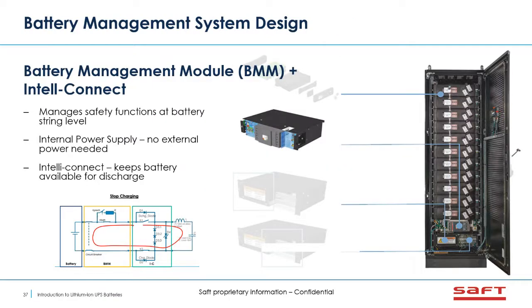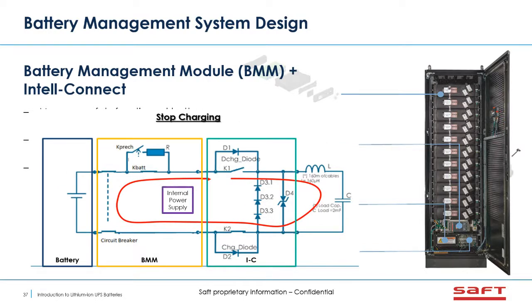A little bit about our BMS: this is where all the safety functions are built in. The key thing we designed into our system is that it has an internal power supply, so we don't require any external power supply going to our cabinet. The other thing unique to our product is IntelliConnect, which keeps the battery available for discharge. If I blow up the schematic here, the dark blue line is the battery modules, the yellow is the BMM, and the green is the IntelliConnect. The internal power supply is inside the BMM, but we can manage or even stop charging of the UPS through this K1 contactor, and the battery can still discharge through the diode.